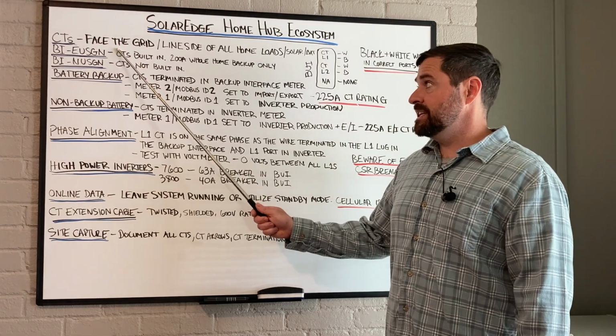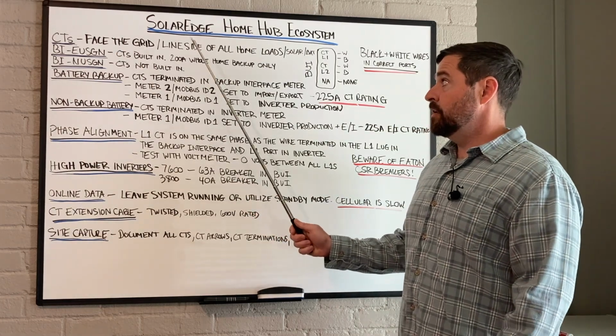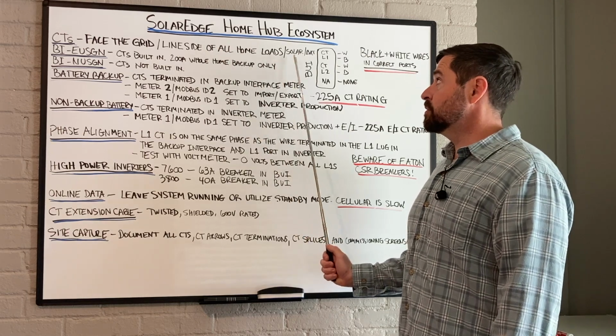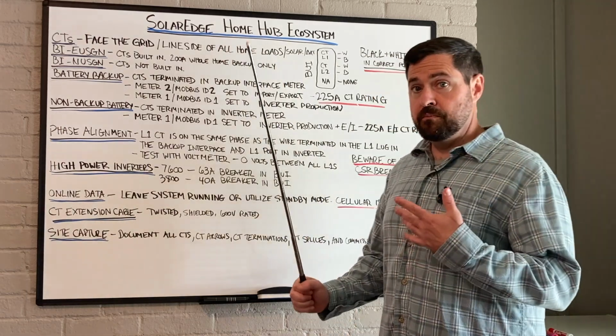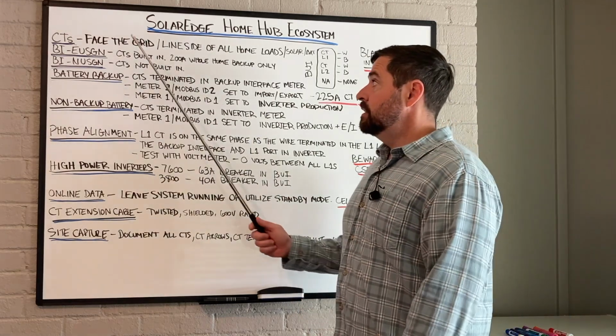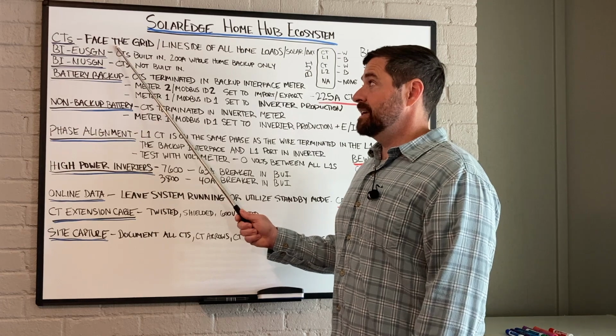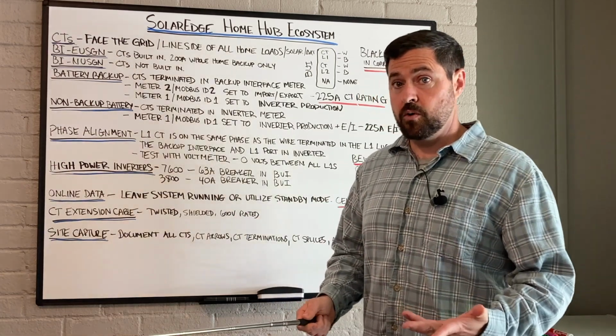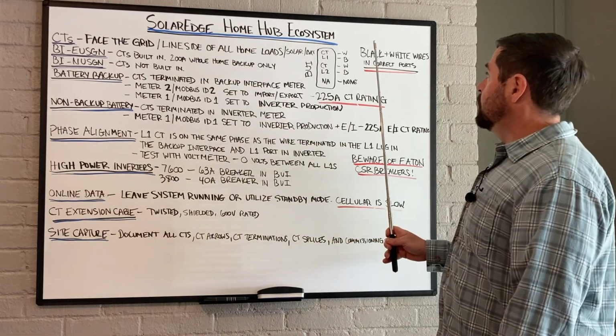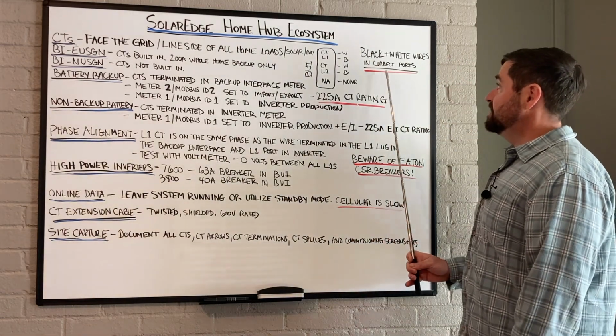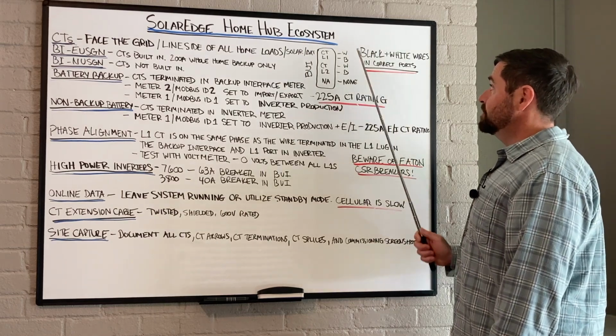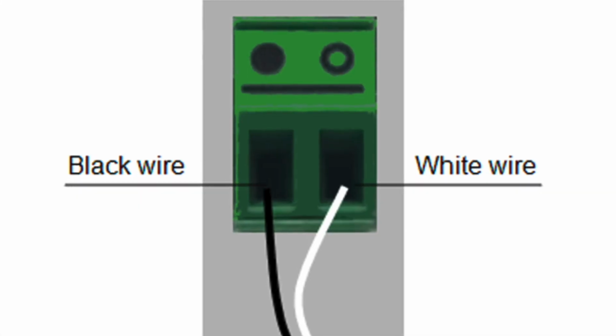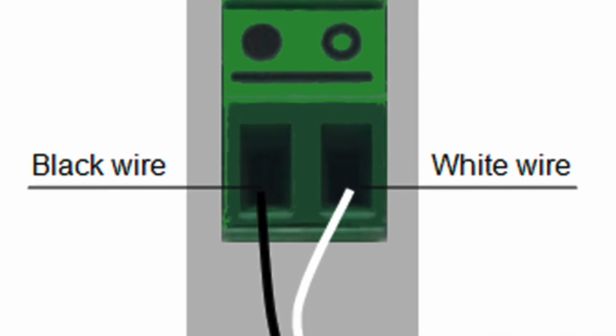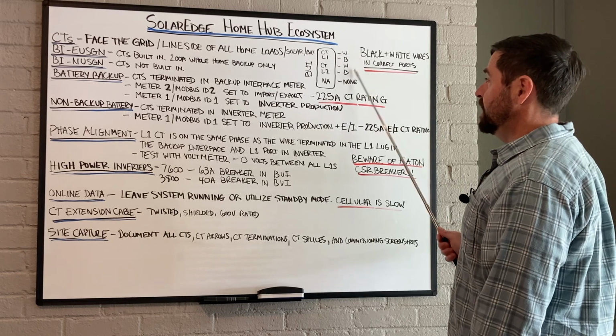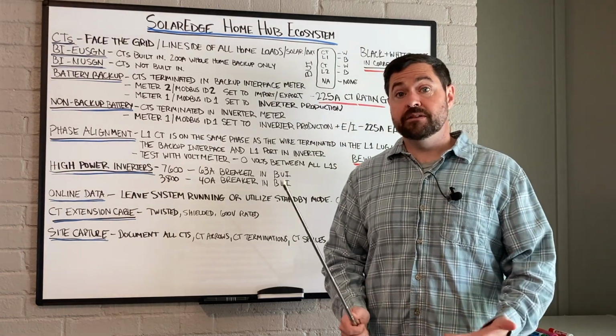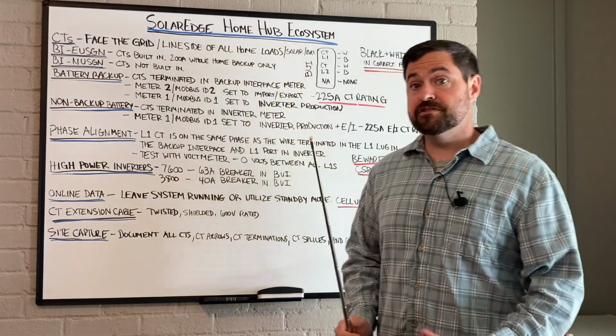Consumption CTs always need to be on the line side of all home loads, solar, and batteries for battery backup installations. The SolarEdge CTs need to face the grid, or away from the customer's home. The black and white wires from the CTs need to be landed in the correct ports. You'll see a little sketch here with white, black for the consumption CTs. Switching the white and black wires is the same as pointing the CTs in the wrong direction. That would be reversed polarity.